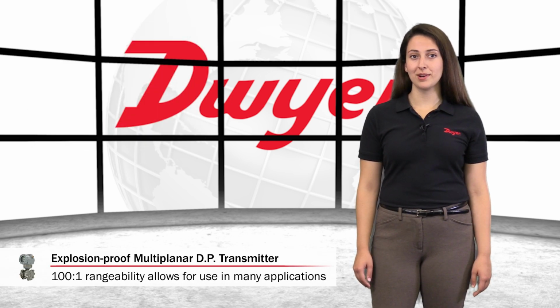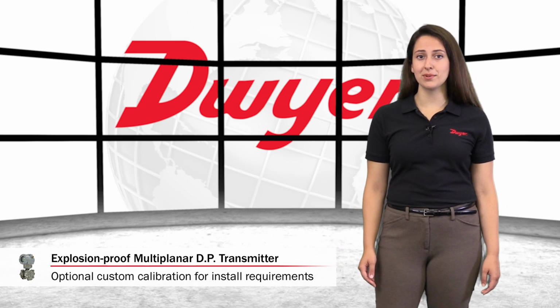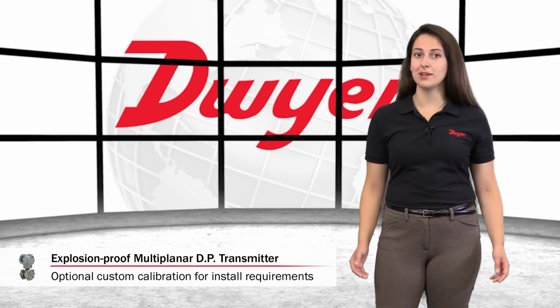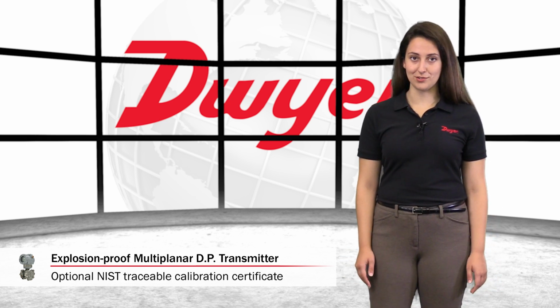The 100-to-1 rangeability allows this smart transmitter to be configured to fit almost any application. In addition, units can be pre-configured by the factory to match the requirements of the application to minimize installation time. Units also have the option to come with a NIST calibration certificate, ensuring a high measurement quality.